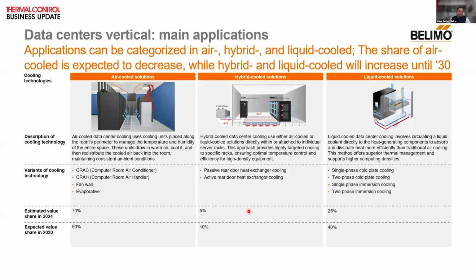If you look at the estimated values from last year, from one of the surveys we have conducted, air cooled, because this is a traditional solution, has the maximum market share, but this is what the future is going to be. So these figures will be swapping places, no doubt about that. And if you see the expected values in 2030, the picture is clearly told. We are still keeping some percentage for air cooled, because even if you are using the rear door heat exchanger, the entire data hall has to be air cooled. There is no option for that. So that's why we see air cooled solutions will still be there in the system.